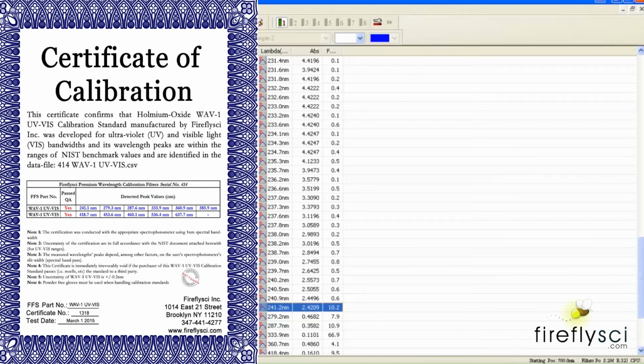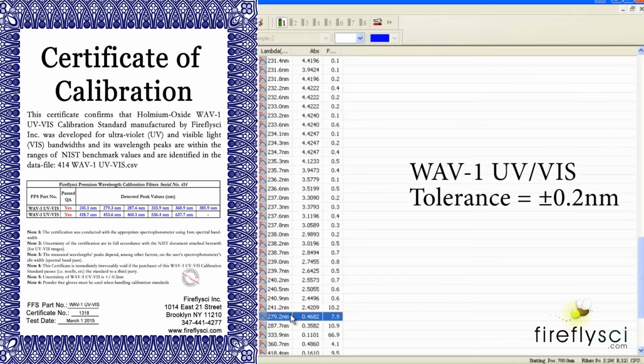Now we'll go ahead and look for the next peak, which should be around 279 nanometers. And we are showing a peak here, 279.2 nanometers, and the Certificate of Calibration shows 279.3 nanometers. Given the tolerance of ±0.2 nanometers, this peak is also correct. We'll go ahead and do one more peak at 287 nanometers, and we have that one right here. And we have 287.7 nanometers in the machine, and on the Certificate of Calibration we have 287.6 nanometers. So again, this peak is 100% correct.